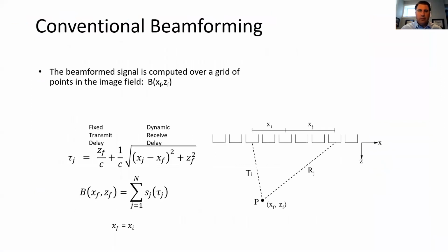this new platform. A little bit of work from Stuart's group in Toronto. This is, again, so apologize for the math here, but just to give you a sense of what we call conventional beamforming. I've mentioned beamforming a few times, but I'm sure most of you are familiar, but if not, really what we're talking about is a series of ultrasound elements. This is the so-called array that we talk about. And as we're firing ultrasound waves, essentially we're solving a geometric problem, trying to understand how long did a particular wavefront from a particular element travel, and then making those corrections such that when we get back to the receive side and bring those signals into the system, we can use these geometric equations to correct for those time delays and essentially form our image.